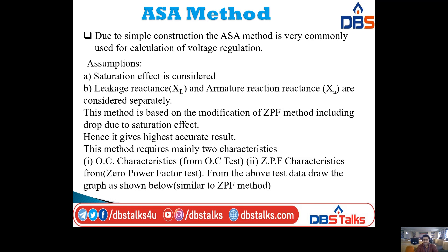The ASA method (American Standard Association method) is very commonly used for calculation of voltage regulation due to its simple construction. It assumes two conditions: first, the saturation effect is considered; second, leakage reactance XL and armature reaction reactance XA are considered separately. This method is based on a modification of the ZPF method, also called the Potier triangle method.